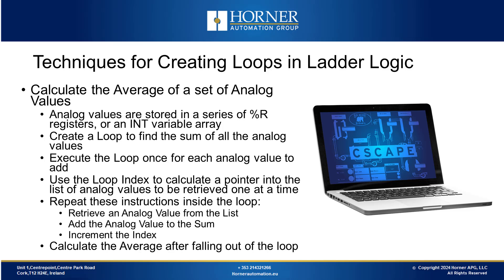For our first demonstration, we will be using a loop to calculate the average on a set of analog values. To calculate the average, we find the sum of the values and then divide that sum by the number of values. We will use a for loop to calculate the sum. We will have a series of analog values stored in an integer array using variable-based ladder. The loop will go through the array, retrieve values one by one, and add them together. Instructions repeating inside the loop will retrieve an analog value, add it to the sum, and increment the index. When we fall out of the loop and have the sum, we will then calculate the average.